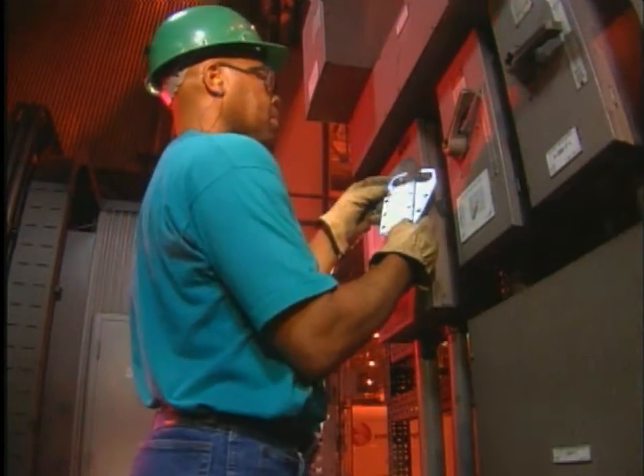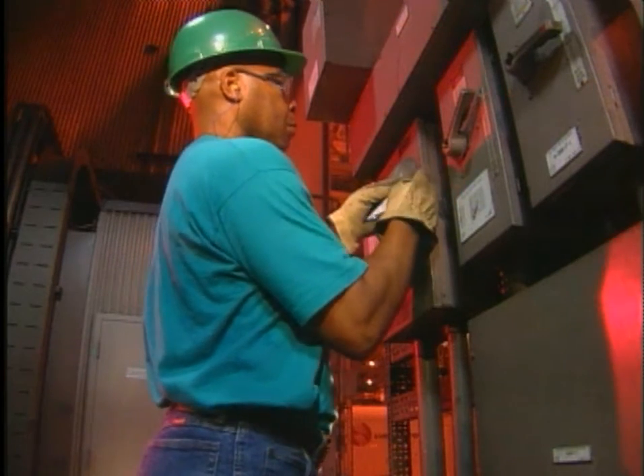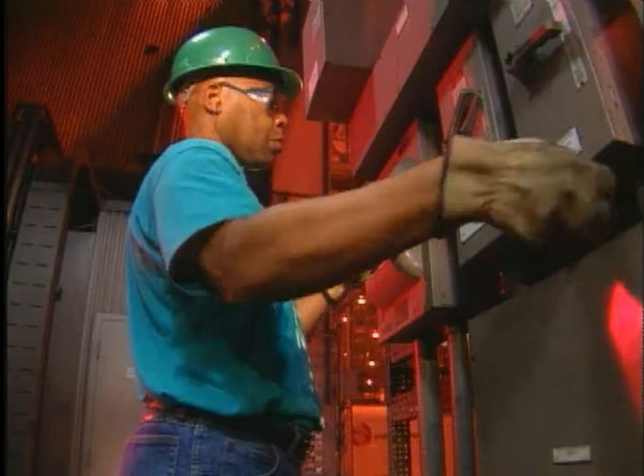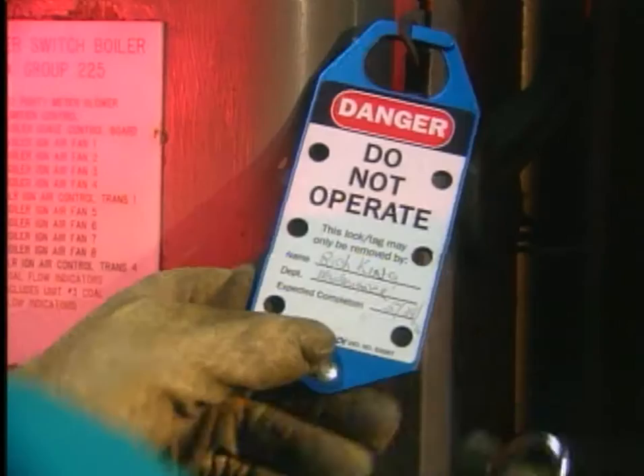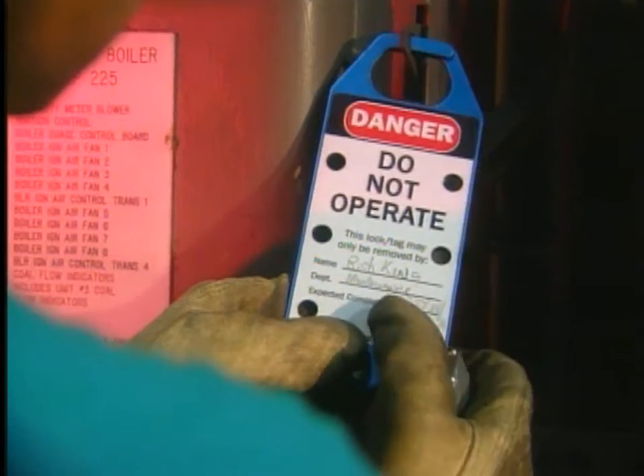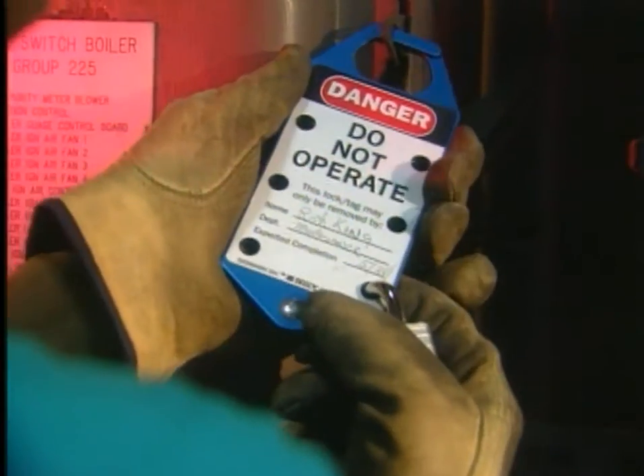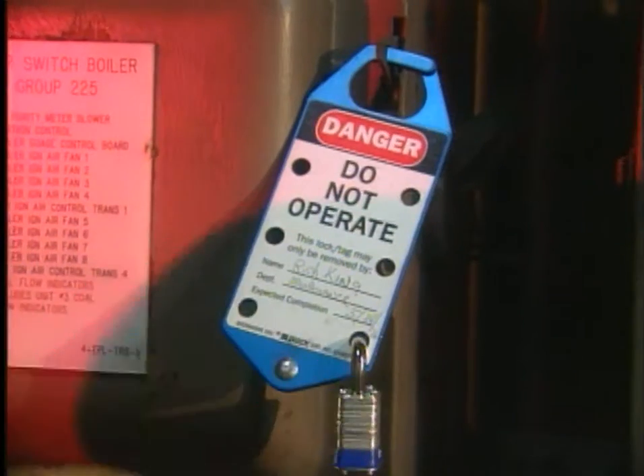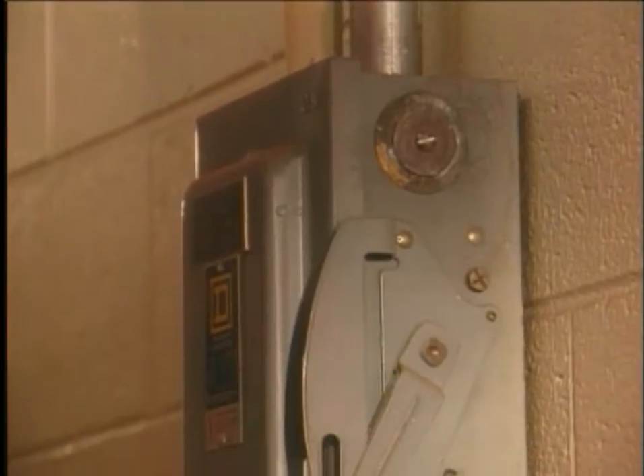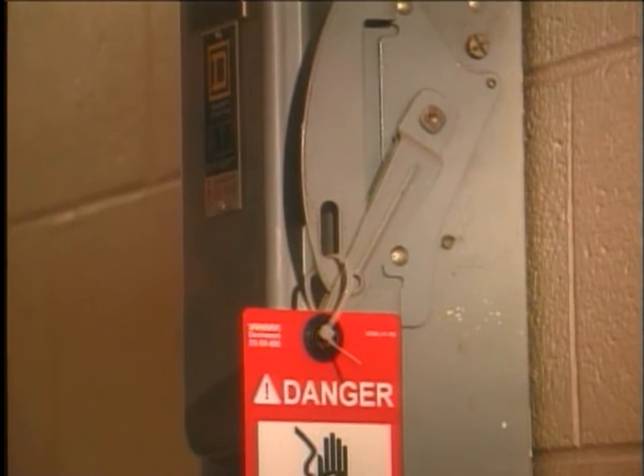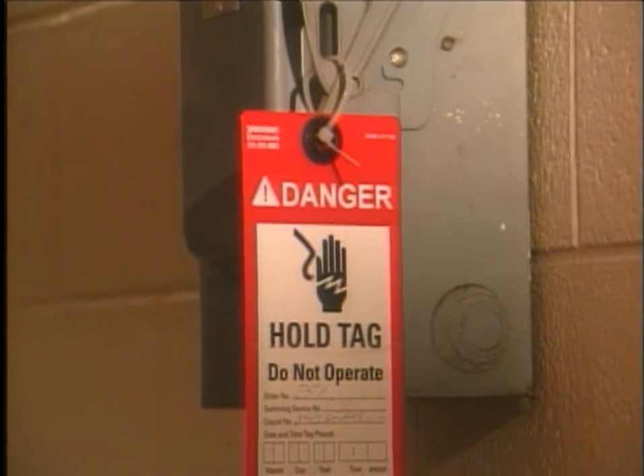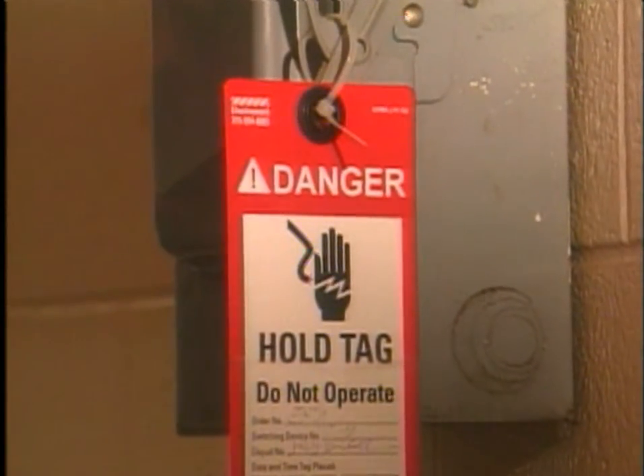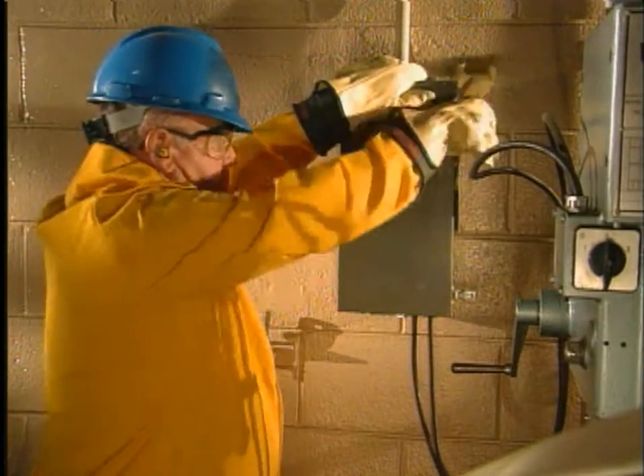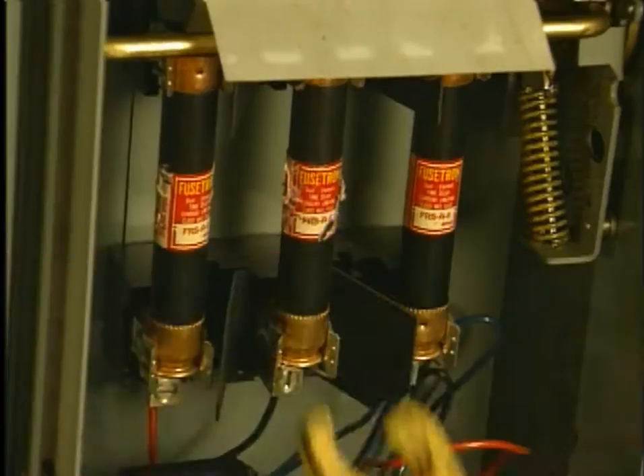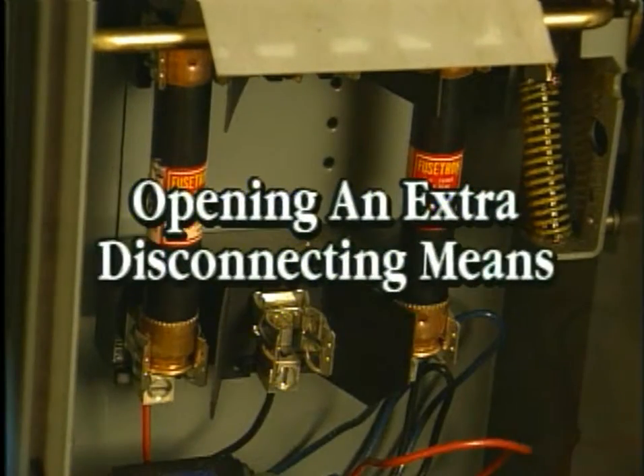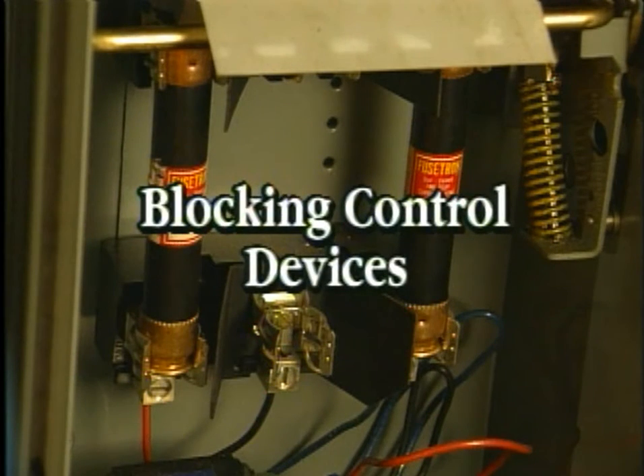Work experience has shown that lockout-tagout can save your life. Before working on circuits and equipment, follow your facility's procedure to the letter. To be safe, a lock and tag are always placed on each disconnecting means, such as a switch or circuit breaker, which could energize the line. In some facilities, tagging alone is permitted if it is demonstrated that tagging provides the same measure of safety as locking and tagging. In that case, additional safety measures must be taken, such as removing fuses, opening an extra disconnecting means, or blocking control devices.